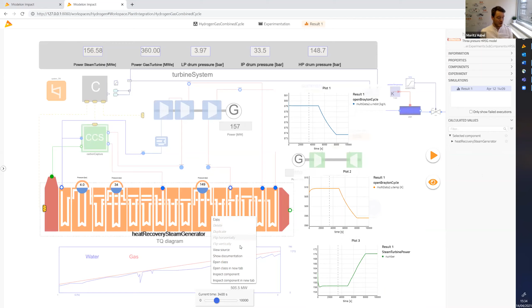That's just one of the challenges you face when retrofitting or gradually increasing the hydrogen content in an existing plant—you need to check the design of your heat recovery steam generator.